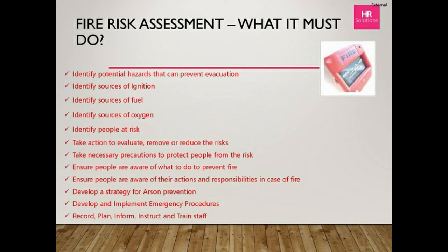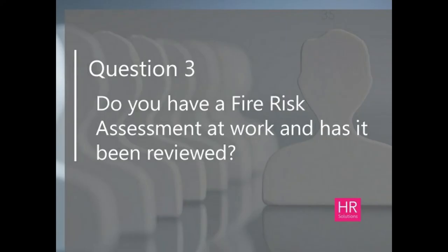A fire risk assessment should contain: identified potential hazards including sources of ignition, fuel, and oxygen; people at risk; evaluation and reduction measures; precautions required; training, information, and instruction for staff; emergency procedures; and an arson prevention strategy. When you receive your fire risk assessment from a competent company, ensure it has all these sections. At the back there should be a matrix or action plan with recommendations to achieve compliance over one, six, and twelve months.